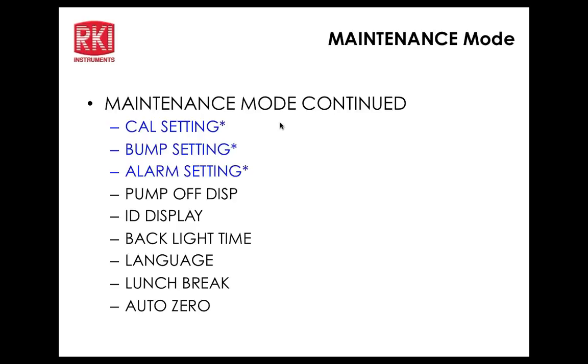And 0 suppression, center that. So right now it's 2%. Right now it says 0 for H2S and 2 for the rest of the sensors. So typically 2% 0 suppression is the default. And what that means is typically it keeps the units reading 0. If there's a little bit of sensor drift occurring that's less than that range, a 2 or 1, then it will just be suppressed to read 0. Okay? In fixed systems, that applies to the negative range as well. If they read negative, they'll also be suppressed to read 0.